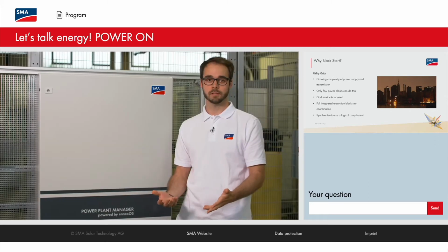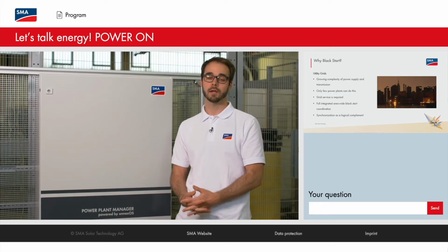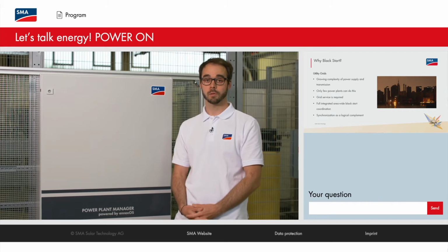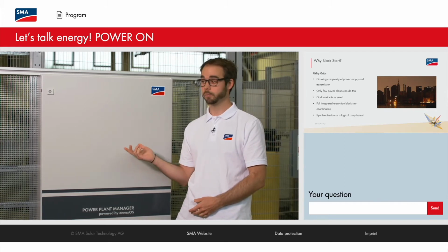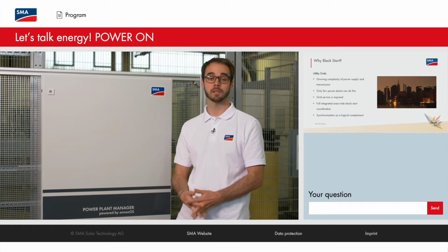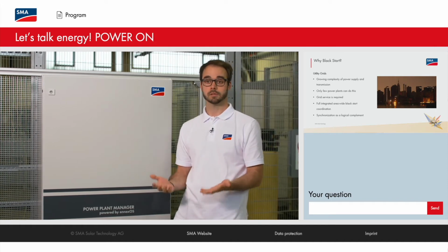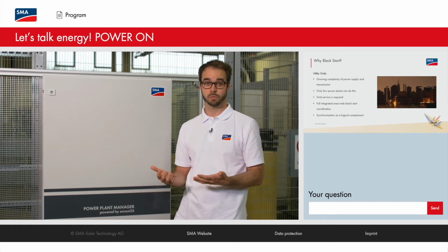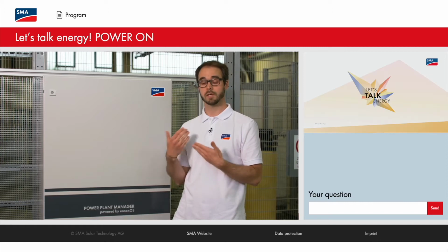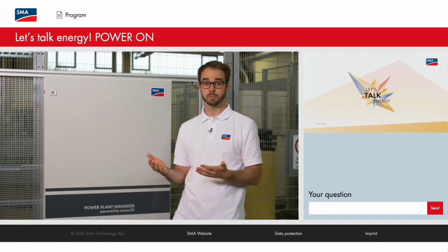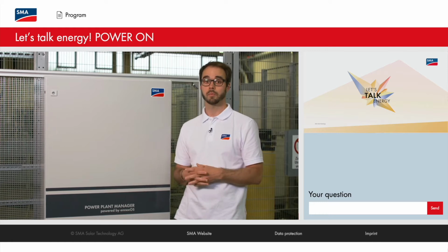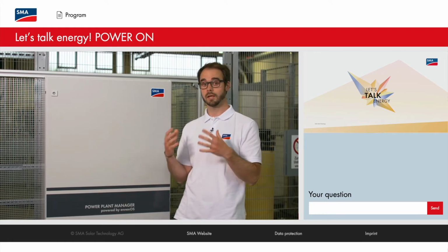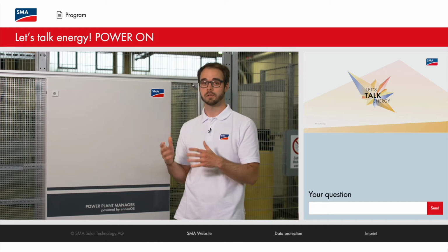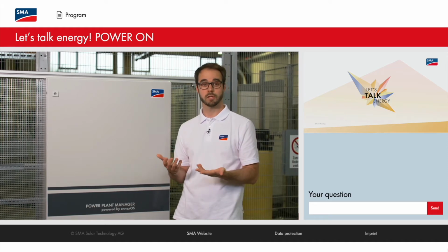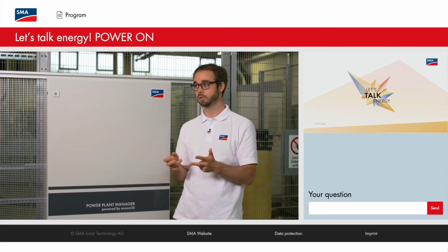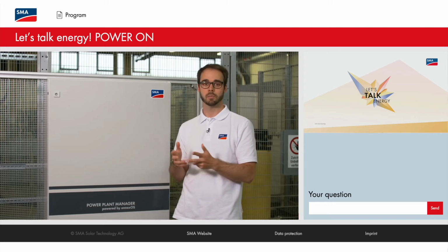What we just simulated is the black start functionality and the synchronization process, which is also coordinated by the Power Plant Manager, right here beside me. Basically what it does is coordinate all the transitions within a hybrid system: the starting of inverters, the synchronization between inverters, the load sharing, but it also synchronizes the whole island system to the overlaid grid.